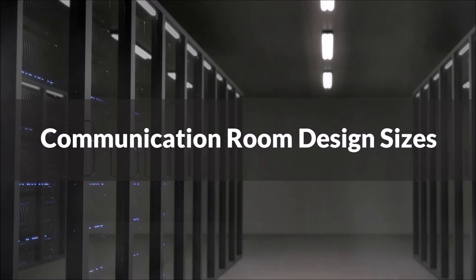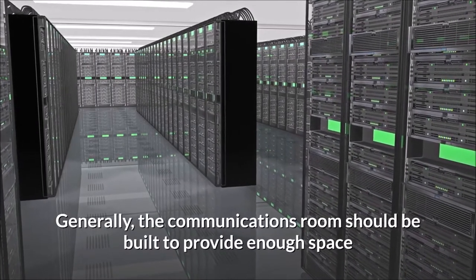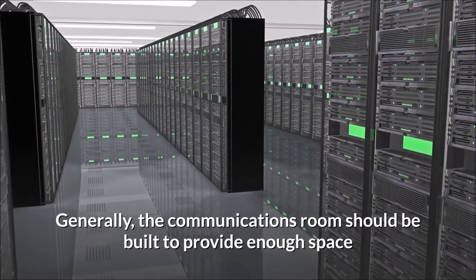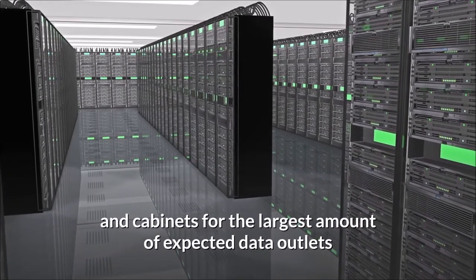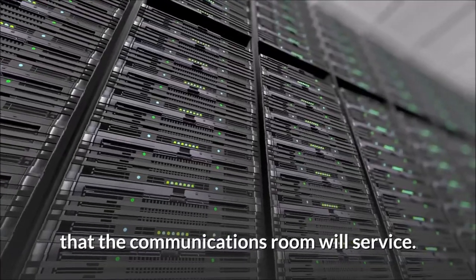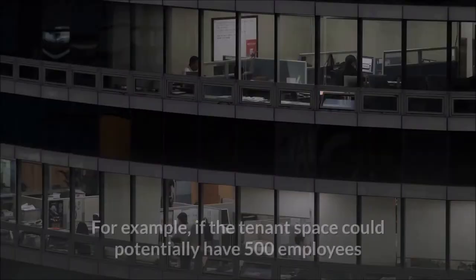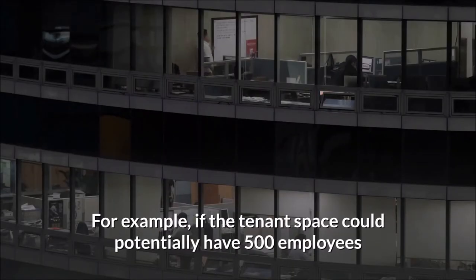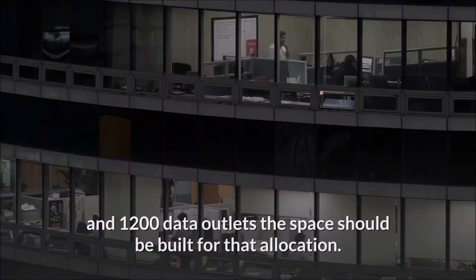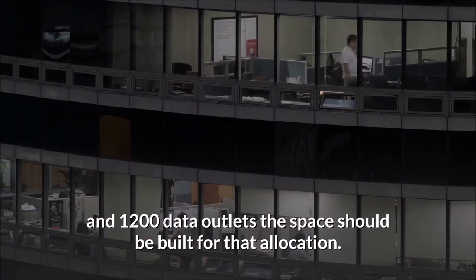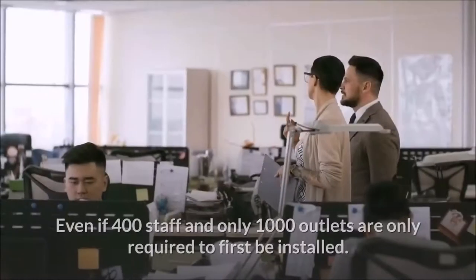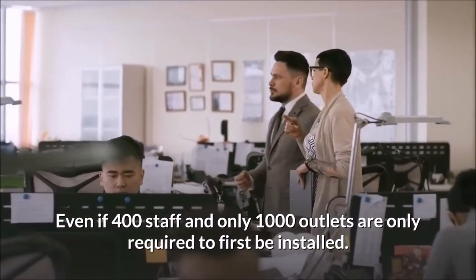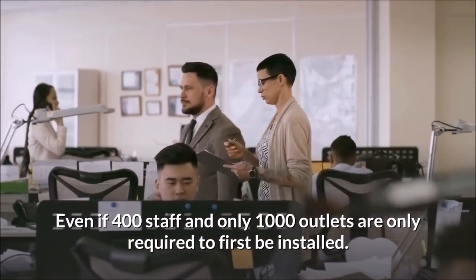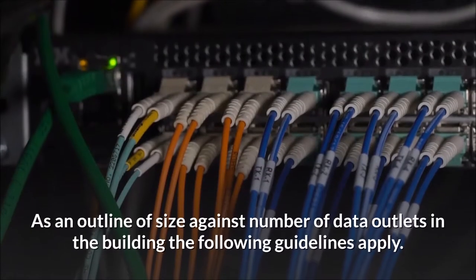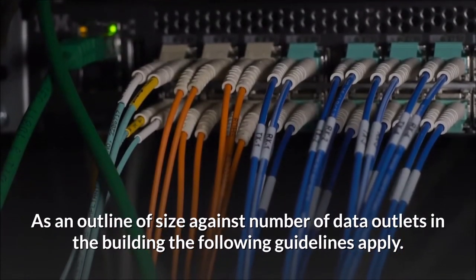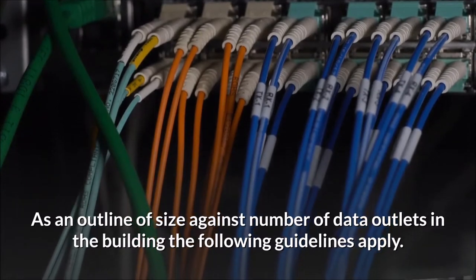Communication room design sizes. Generally, the communications room should be built to provide enough space and cabinets for the largest amount of expected data outlets that the communications room will service. For example, if the tenant space could potentially have 500 employees and 1200 data outlets, the space should be built for that allocation, even if 400 staff and only 1000 outlets are required to first be installed. As an outline of size against number of data outlets in the building, the following guidelines apply.